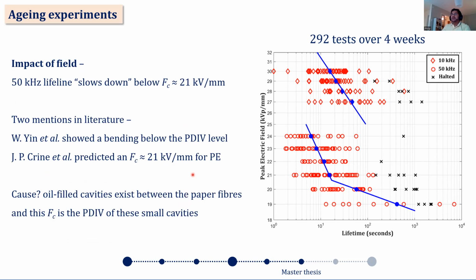The second kind of observation, which I found very interesting, was the impact of field. If you look at the 50 kilohertz line, you can see that between 20 and 21 kV per millimeter there is a transition, and it looks like the life line is slowing down below this critical field value. I did a lot of reading in the literature to see similar bends, and I found two of them. The first, I think in 1997, showed that this level could be the partial discharge inception voltage level, above which partial discharges greatly accelerate the aging, but below which they don't happen and don't accelerate aging, and this could cause a slowing down of the life line.